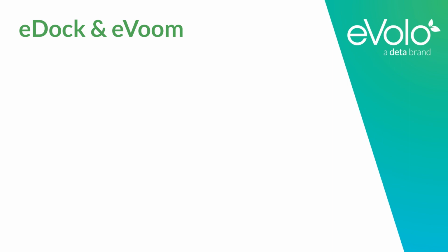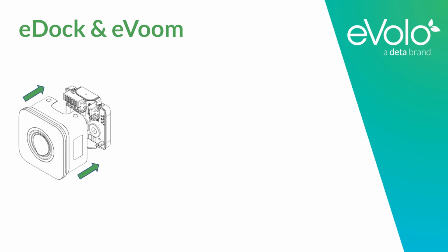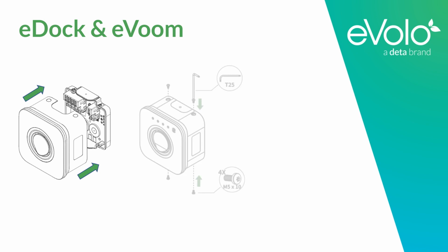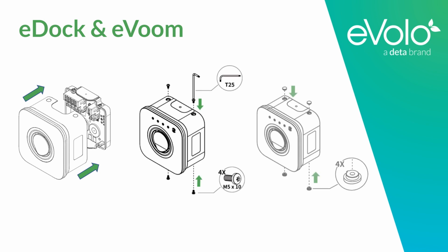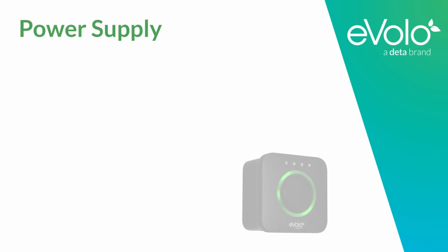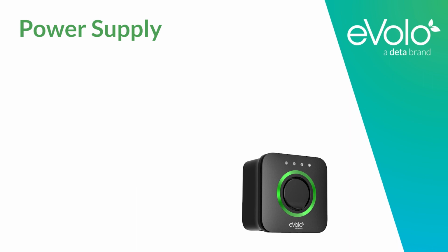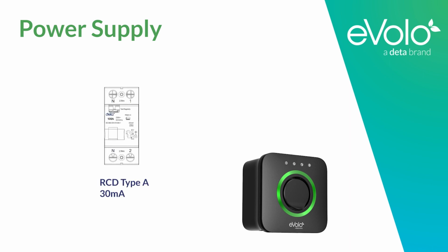Once the data cable is connected, simply push the charge point onto the mounting base, ensuring the contacts line up before fitting the security screws and inserting the caps as explained earlier. It's imperative that charge points have an RCD protected supply that must be Type A versions with 30 mA tripping current. If fitting an Evolo charge point to an existing installation, check to see what type of RCD it has and change it to a Type A RCD if necessary.